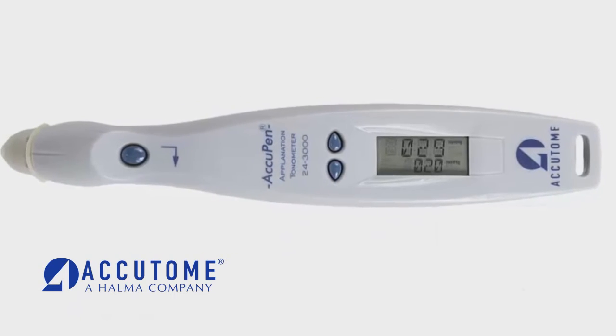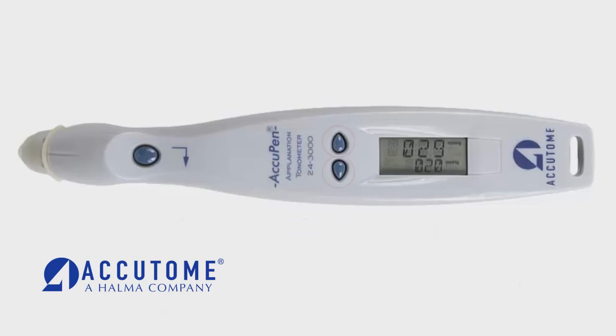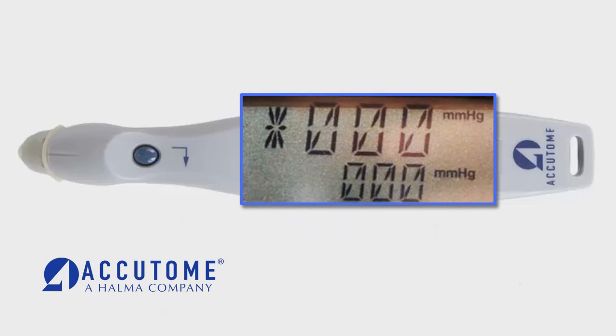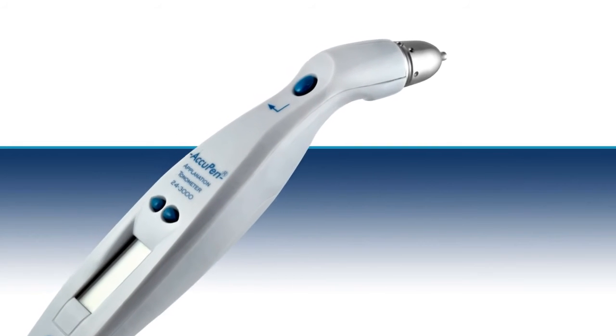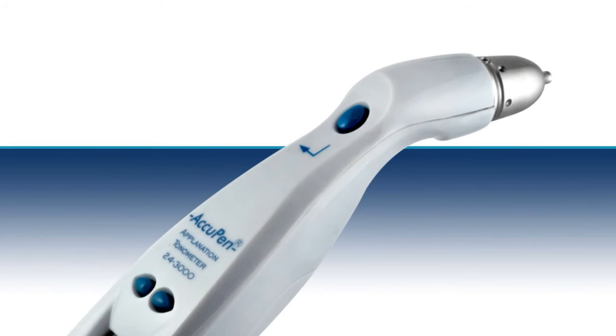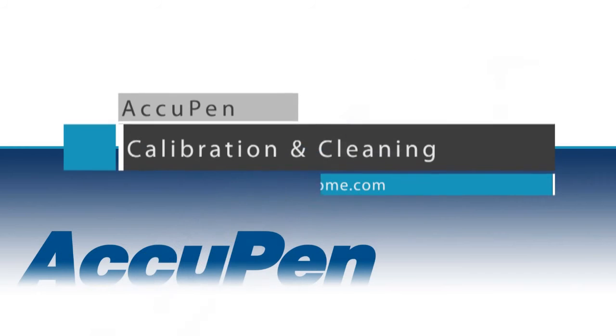To clear the accupen completely, hold down both arrow buttons for approximately 3 seconds. The unit will chirp indicating the measurements have been deleted. Once 6 zeros appear on the screen, the unit is ready to acquire a new measurement. If the accupen is capturing erratic readings, not acquiring measurements, or an error message is displayed, the unit may need to be calibrated or cleaned.